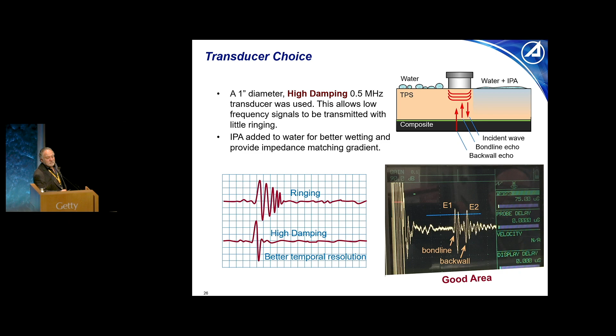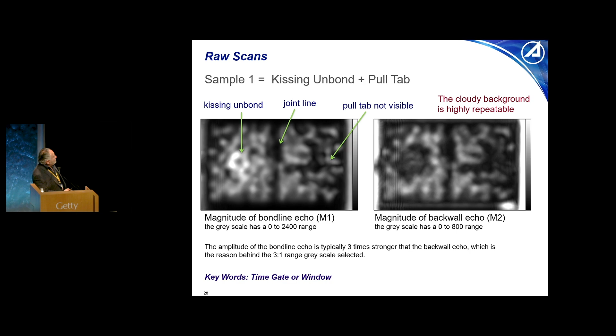So these are the two echoes. When you gate the signal on the first echo, gate the signal on the second echo, and take the ratio, this is the image we get. Now, this is not a random scan. This is a very repeatable scan. This cloudiness and murkiness represents the inhomogeneity of the part itself. So this is very repeatable if you scan it several times. But when we take the ratio, where M1 is the magnitude of the first echo and M2 is the magnitude of the second echo, you start to see something that emerges.